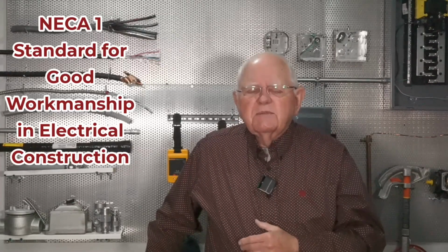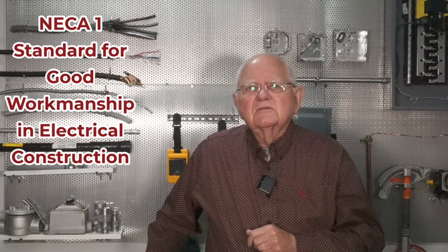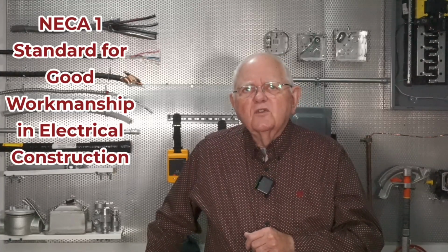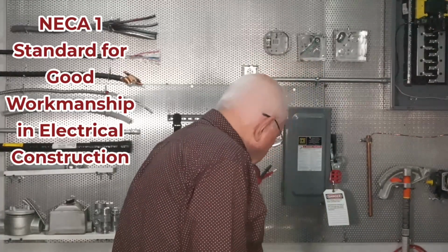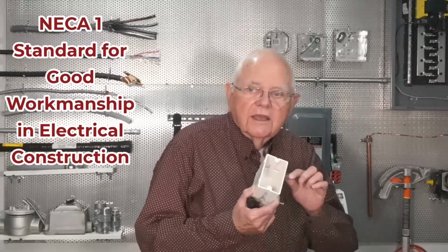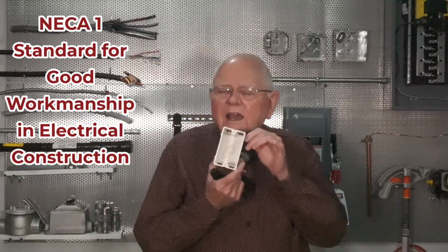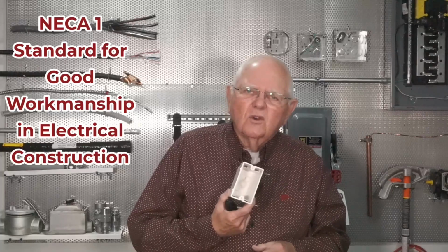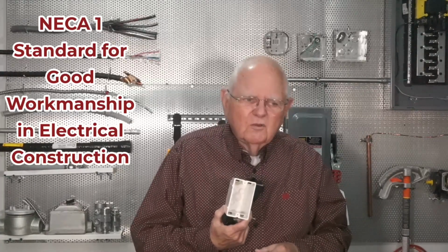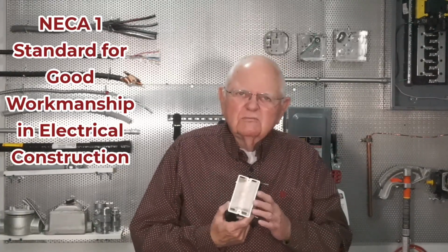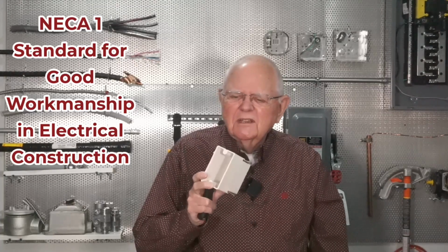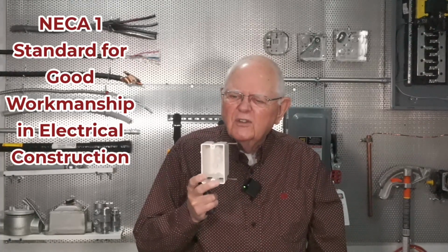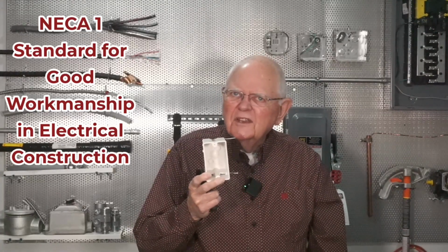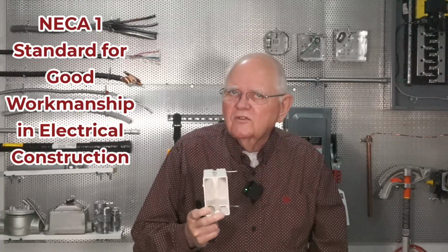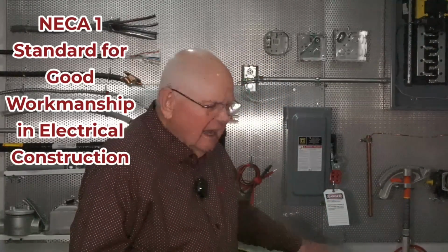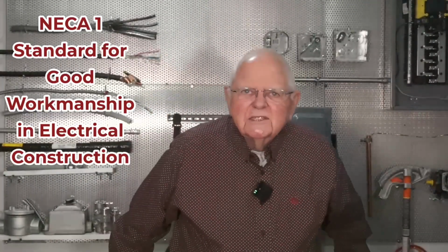So maybe my project specifications on my drawing says put a light switch. Okay? I'm going to put a light switch by the door. Where do I put it? So I have to take a box and I have to mount this box somewhere. How close do I put it to the trim of the door casing, and the height, where should it go and so forth? There's nothing in the code that says it has to be true and plumb and all of that. And there's really nothing in the code that gives me any height requirements and so forth, but my NEIS standards do. So we're going to pay attention to them.